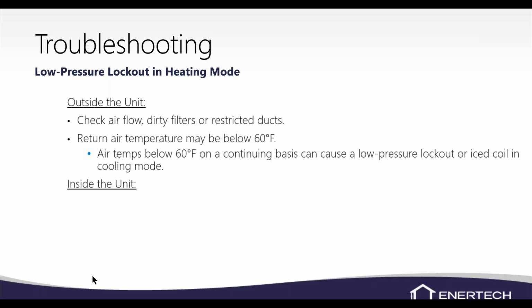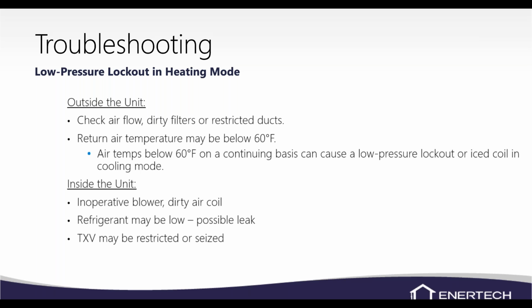Inside the unit, again, inoperative blower, dirty air coil, something along those lines. Obviously, refrigerant low, make sure we're looking for a leak. And TXV is restricted. I'm sure none of you guys have seen a TXV restricted before, but occasionally we have that problem. Low pressure switch or a board problem as well.